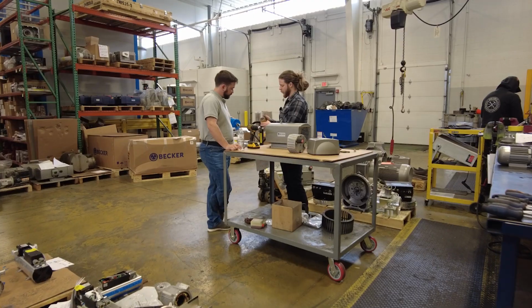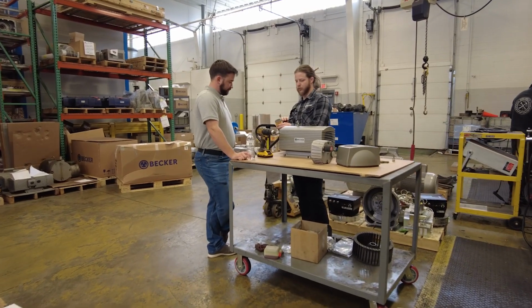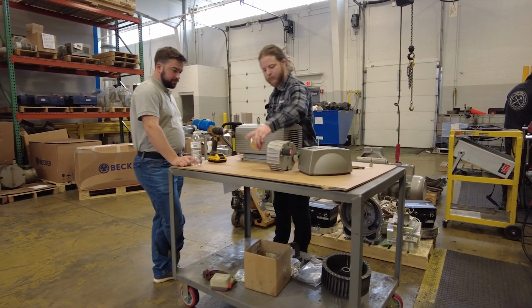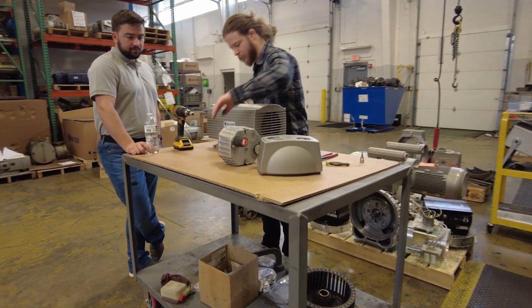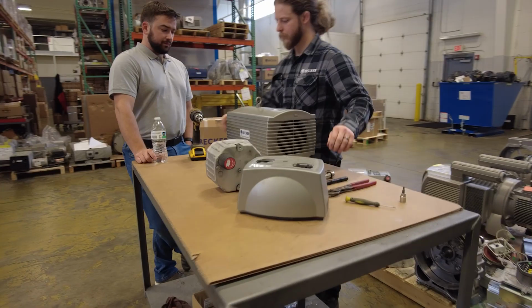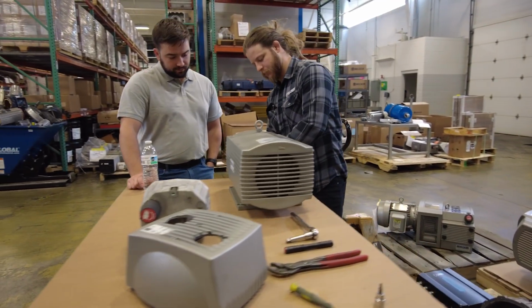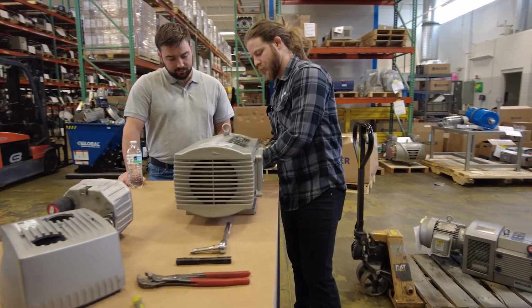So just checking. Usually from the factory we ship them wired for 460 volt, but it's very common for customers to have 208 volt or 230 volt power, and they're not always double checking to make sure the configuration is correct. The problem with that is if it's not wired for your voltage, you'll burn up the motor pretty much immediately. A lot of times these kinds of mistakes are happening because customers don't know to ask or they're not working with a certified electrician. So we always suggest if you have an electrician that you trust, always work with them to do your wiring and to confirm that the motor is wired correctly.